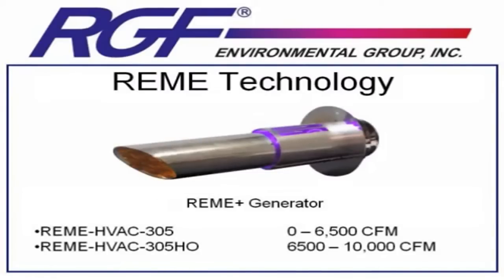REME technology currently comes in two separate sizes: a 0 to 6,500 CFM and a 6,500 to 10,000 CFM rating. Just like the PHI systems, if you're dealing with a job that is 40,000 CFM, you can just add units to total up to the 40,000 CFM you need — in this case, four of the HVAC-305HO. Also like the PHI system, if you are dealing with a high-load application like a smoker's bar or casino, you may need to upsize the REME unit to overcome the extra load of pollutants in the air.